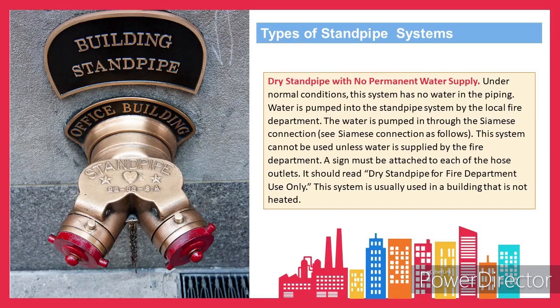The last type is the dry standpipe with no permanent water supply. Under normal conditions, this system has no water in the piping. Water is pumped into the standpipe system by the local fire department. The water is pumped in through the Siamese connection. See Siamese connection as follows. This system cannot be used unless water is supplied by the fire department. A sign must be attached to each of the hose outlets. It should read, "Dry standpipe for fire department use only." This system is usually used in a building that is not heated.